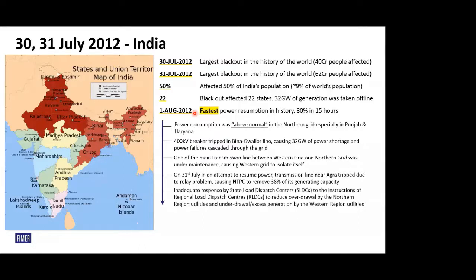What happens is, you always see that the farmers load the grid too much, and you're not supposed to overload the grid. The 11 kV operators, the substation operators, usually end up removing the relay so that it won't trip with under voltage or anything, or keeping it across bigger limits. But there was an abnormal overloading on the northern side of the grid. Also, a maintenance activity was happening in one of the two major 400 kV interconnection lines between the western grid and the northern grid. So basically you had only half a road to travel on, let's say if you're traveling on a highway.